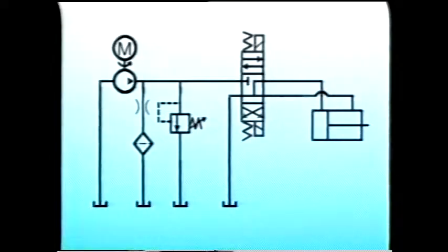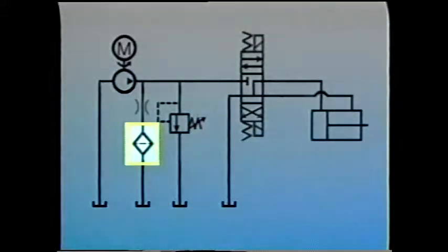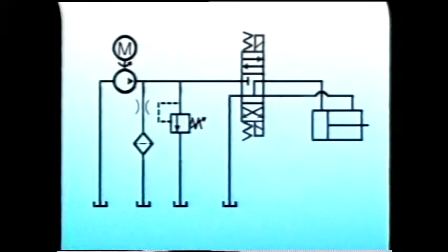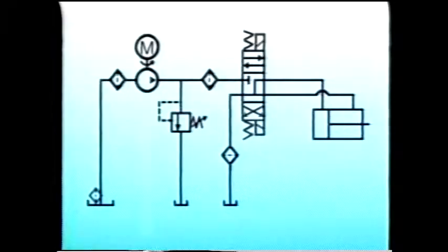Most hydraulic systems today filter all the fluid in the system, but a few still use proportional filtration. In this filtering system, only a portion of the pump's flow is bled off through a filter before being returned to the sump. Proportional filtration is generally not adequate for the narrow clearances of today's hydraulic systems. Instead, full-flow filtration is used.